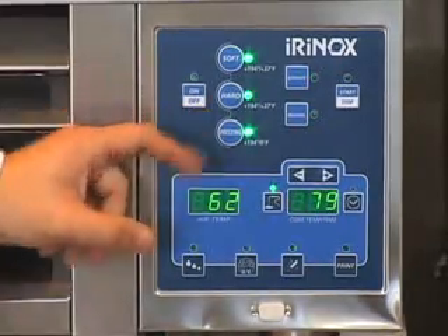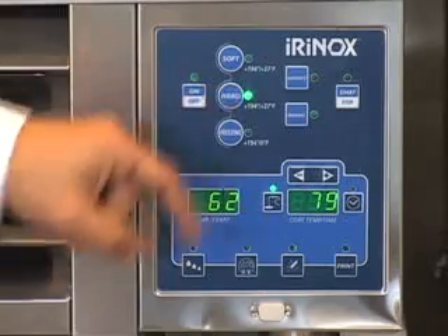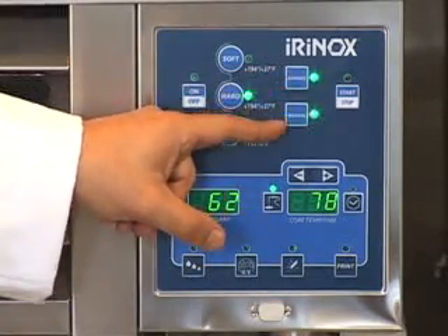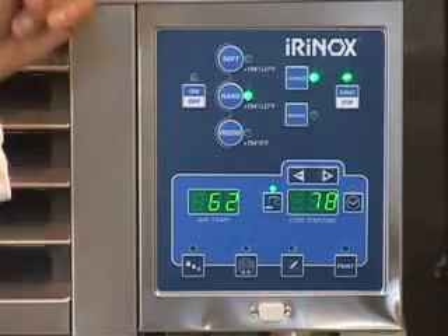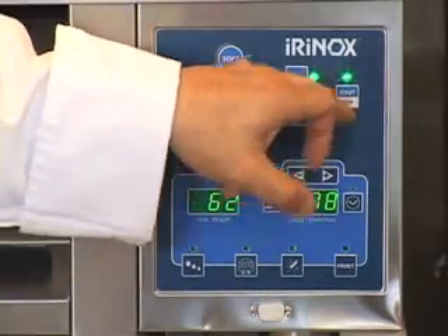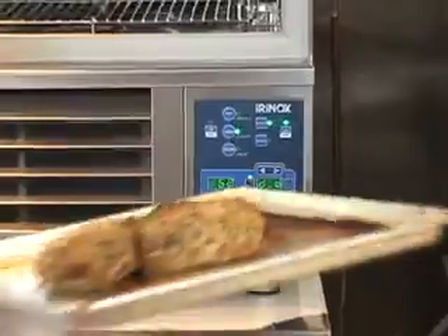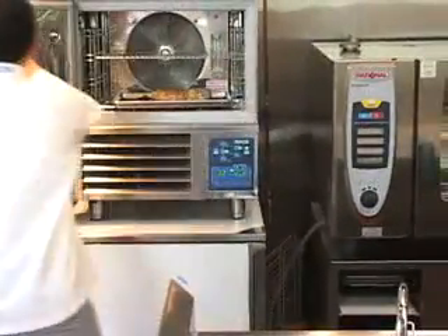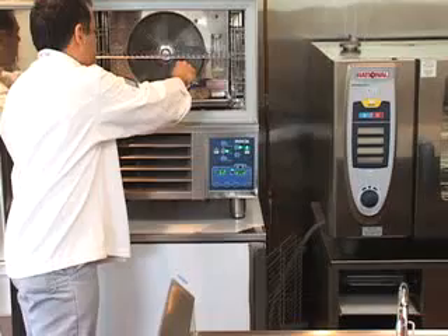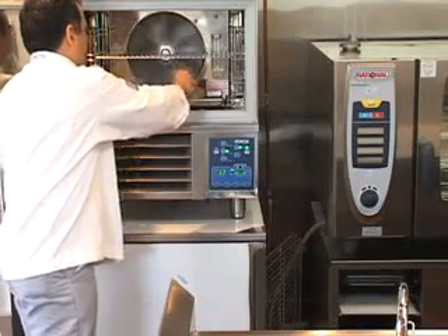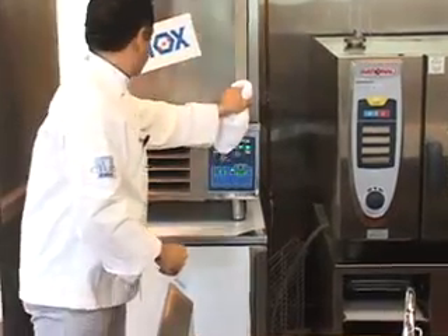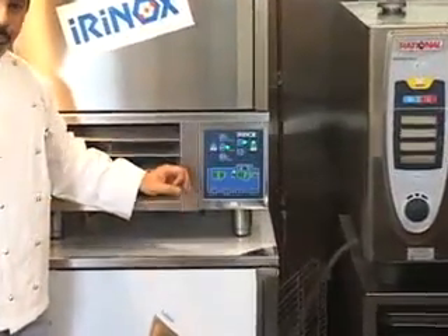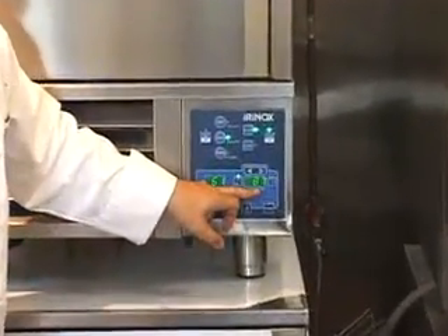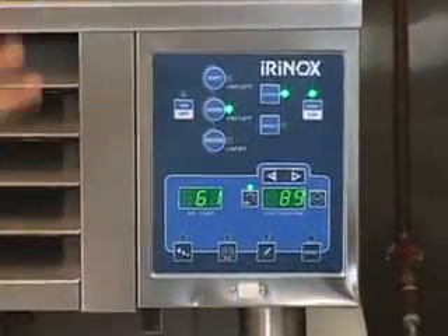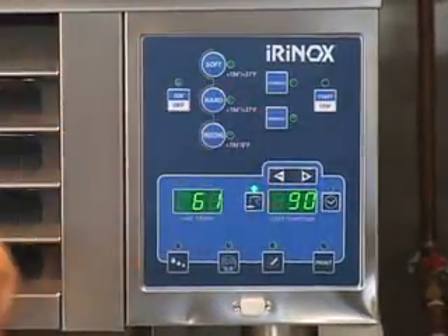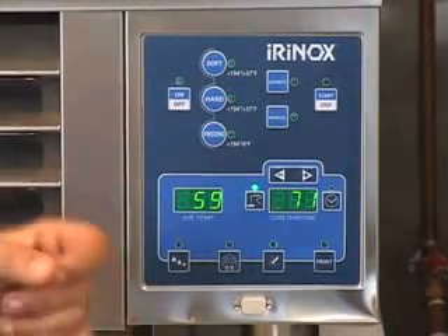I'm going to demonstrate the hard automatic cycle. Again, I choose the hard cycle. I have the choice between automatic and manual, and I'm going to use the automatic cycle, which is going to require the probe. I'm going to hit the start button, and now I have a piece of roast pork. So I'm going to put the pork in the blast chiller. I'm going to take the probe and insert it into the thickest center point of the roast. I now can close the door, and the unit is going to run until the pork core temperature hits 37 degrees. At that point, the unit will go into hold and remain in hold until I come over and I stop the unit. I'm now going to demonstrate the shock freeze mode.